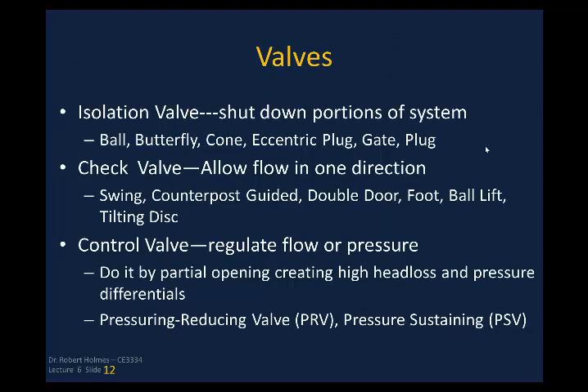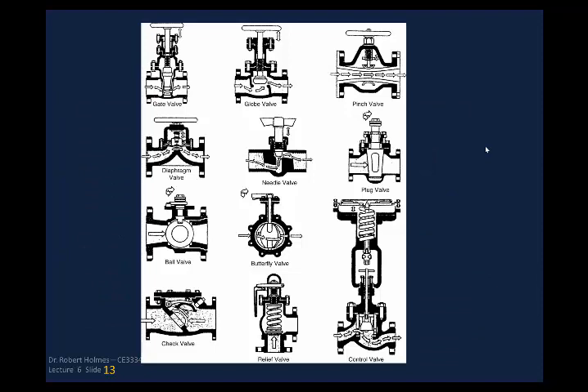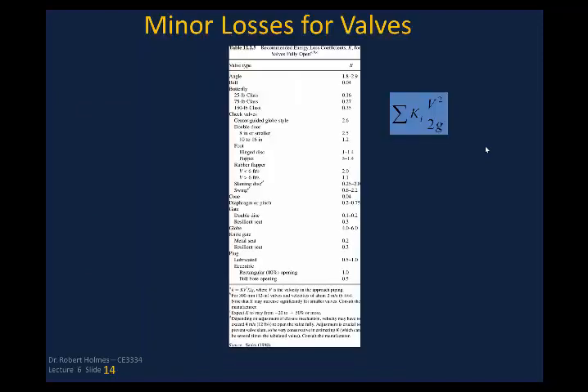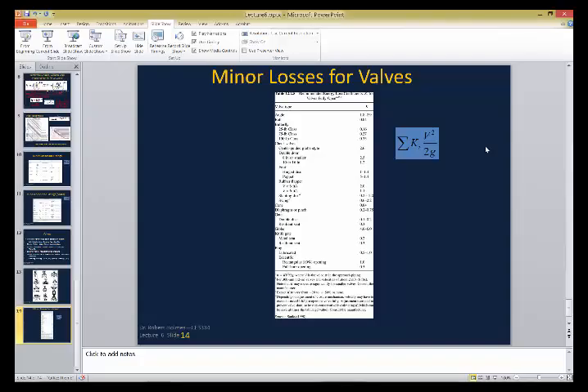When we talk about valves: the isolation valve is used to isolate a portion of the system for repair. The check valve only allows flow in one direction. And the control valve is to regulate flow or pressure. Here are some diagrams and cartoons of what those kinds of valves look like. For valves, same as any kind of fitting — you're going to have a K value, and sometimes they can be quite large in terms of their value for K. That concludes lecture number six.